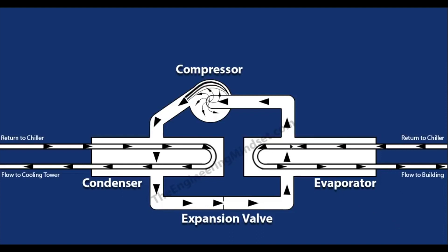Inside the evaporator, the chilled water circuit water is sent up to the AHU to collect unwanted heat from the building. It returns at about 12 degrees, comes back into the chiller, passes through the loop, and by the time it leaves again it needs to be around 6 degrees. The water is held within tubes, keeping it completely isolated from the refrigerant — the two never mix. The water comes in, passes through the tubes, and leaves again; the refrigerant passes through and picks up the heat through the tube walls.